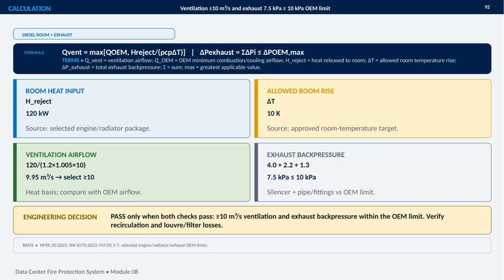The exhaust check is separate. The silencer, piping, and fittings contribute 4.0, 2.2, and 1.3 kilopascals, for a total back pressure of 7.5 kilopascals. This is below the 10 kilopascal OEM limit. The engineering decision is a pass only when both conditions are satisfied, including verification of recirculation and louvre or filter losses, using the listed standards and manufacturer limits.